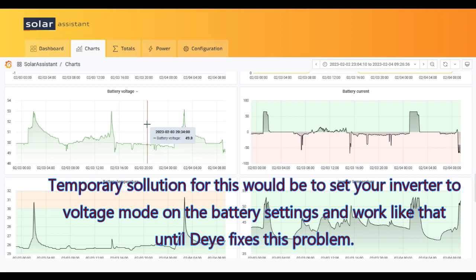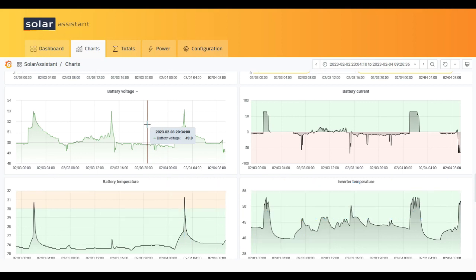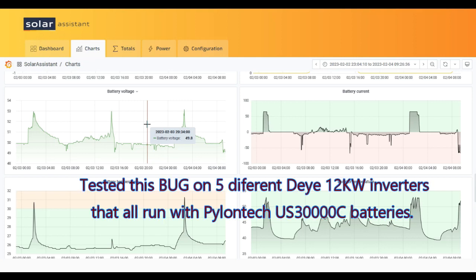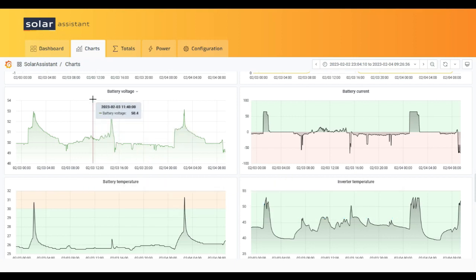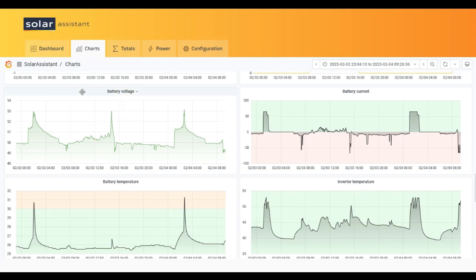I've been talking with Deye and they are working on a solution. This seems to be a general problem because I had this problem on five inverters all connected with Pylontech and they all do the same thing. So Deye inverter connected to Pylontech, watch out for your battery voltage and overvoltages. Thanks for watching guys.